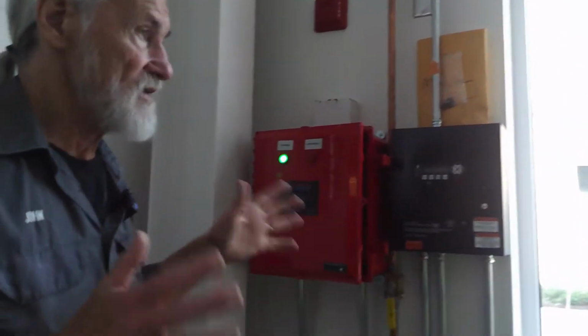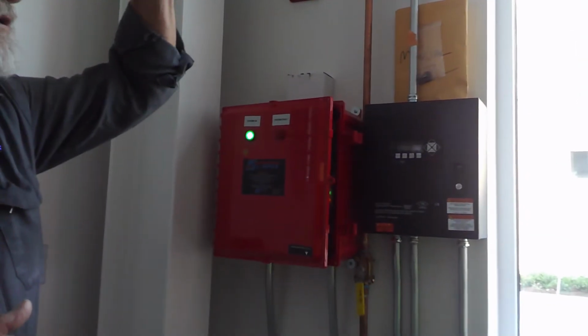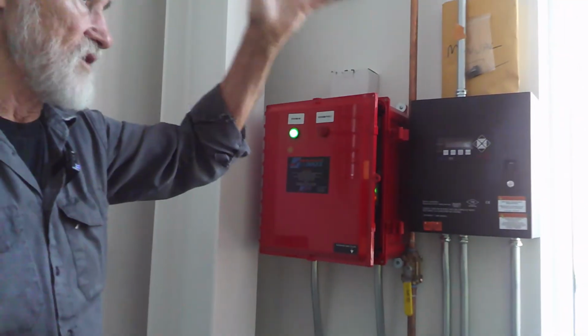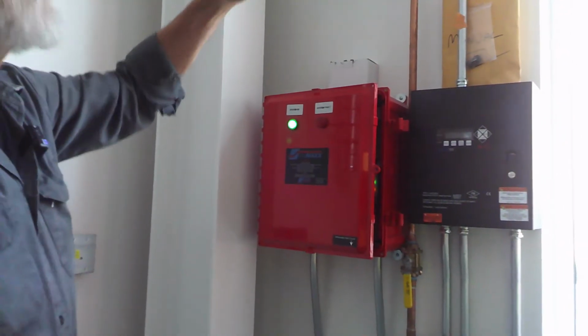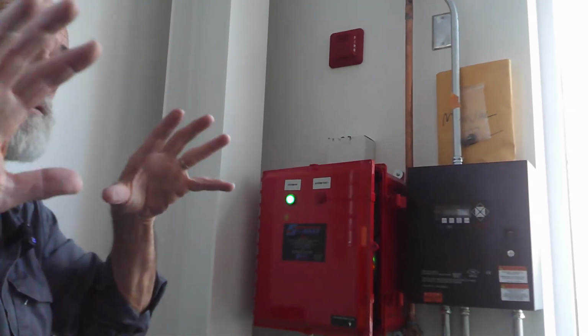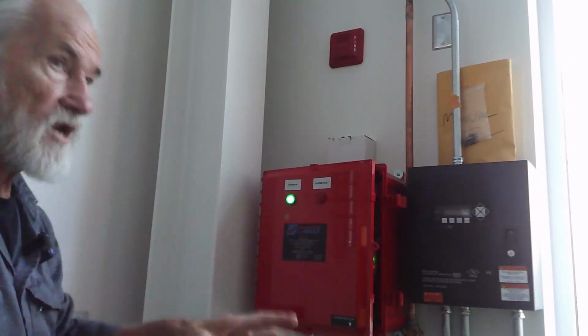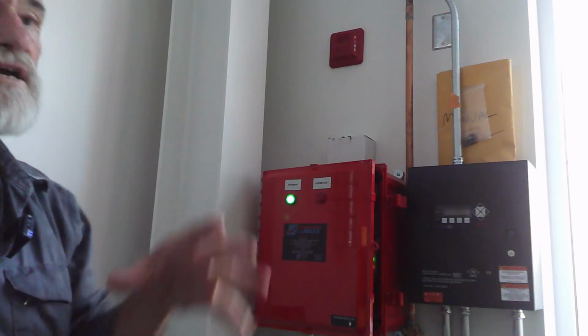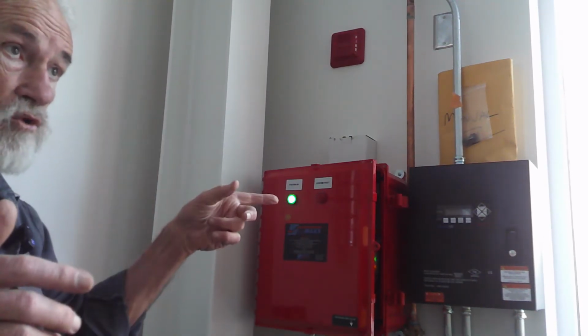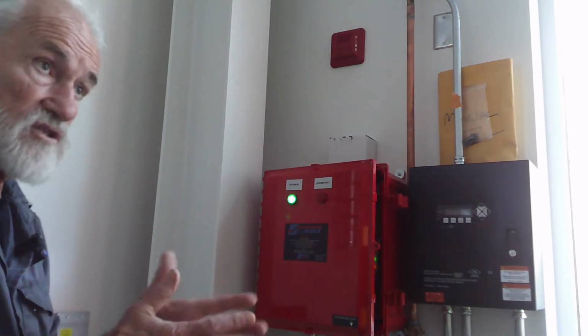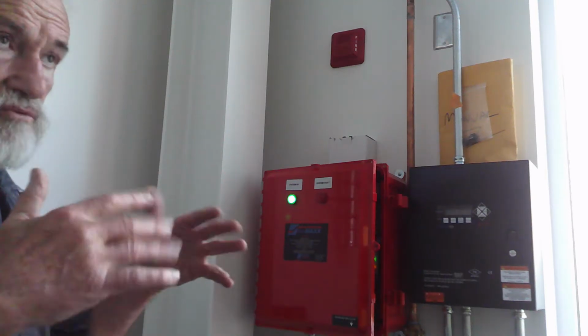No, okay, it has to be out there. It's supposed to be some specified distance from the spark detector. I think I remember this unit being like 23 or 26 feet, so it would be out there. The idea is, if it detects a spark here, knowing how fast the flame would propagate in these conditions - like wood, as opposed to metal filings, which don't have spark detectors - they'd know we've got this much time, we have to allow this much time for the system to sense it and turn the water on, so that when the fire reaches the sprinkler system, it's functioning. So the distance is critical, and it's been set right.